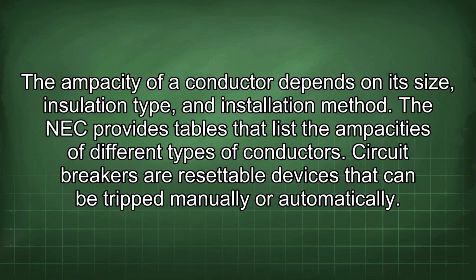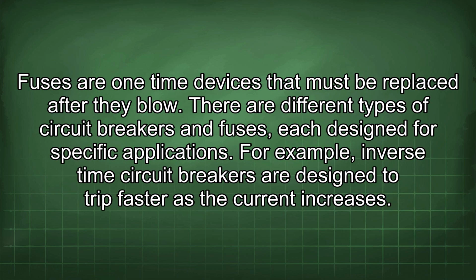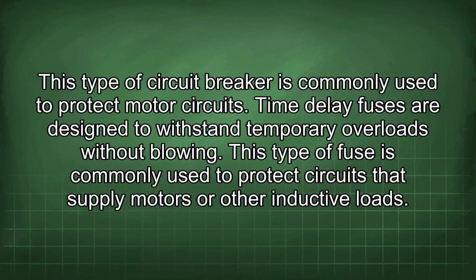Circuit breakers are resettable devices that can be tripped manually or automatically. Fuses are one-time devices that must be replaced after they blow. There are different types of circuit breakers and fuses, each designed for specific applications. For example, inverse time circuit breakers are designed to trip faster as the current increases. This type of circuit breaker is commonly used to protect motor circuits. Time delay fuses are designed to withstand temporary overloads without blowing. This type of fuse is commonly used to protect circuits that supply motors or other inductive loads.